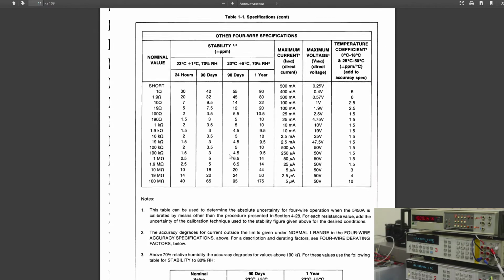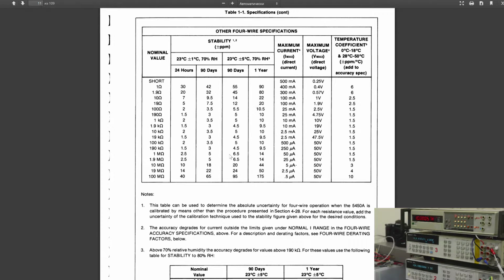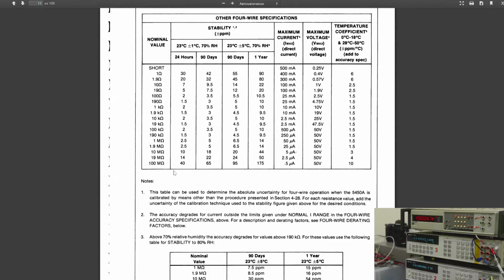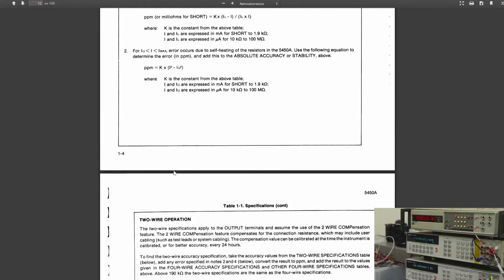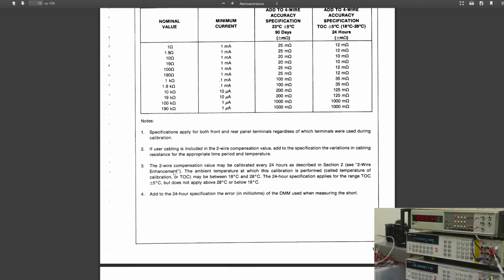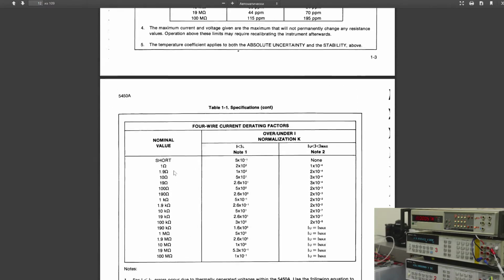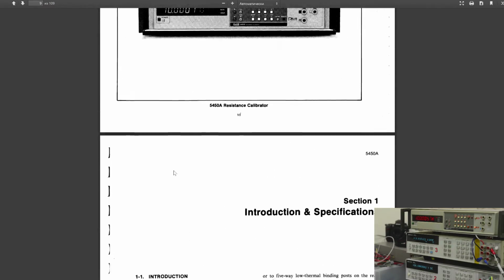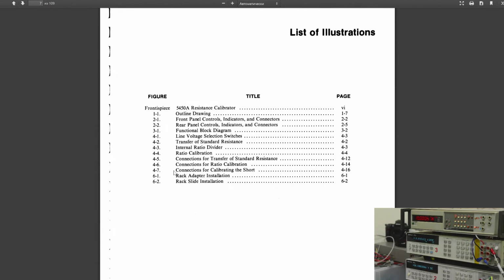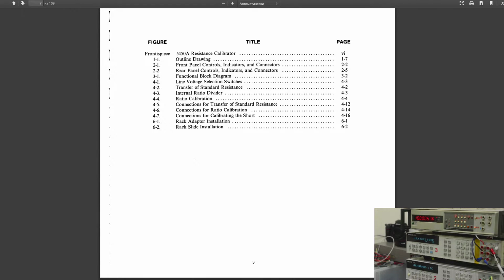That's of course given that it's calibrated properly. You can also see stability for 24 hours. It's easy to maintain 2 ppm in the range from ohms up to 1 mega ohm, which is not bad at all. And the temperature coefficient is a maximum of 10 ppm per degree for the highest, 100 mega ohm, and most of the other resistors are 1.5 to 2 ppm per degree. There are plenty of other specifications. The manual is available on the internet, and anyone who is interested can search for it and take a look. And here's the picture of the unit itself. Alright, let's go back to our meter.